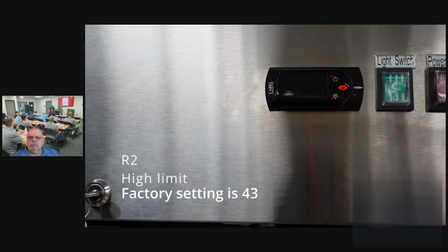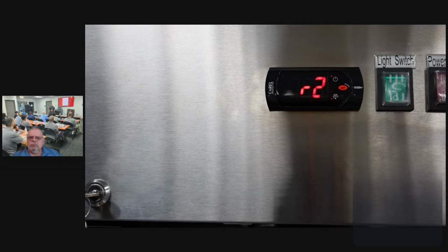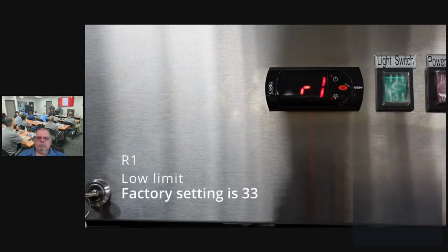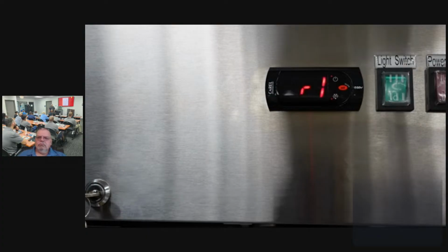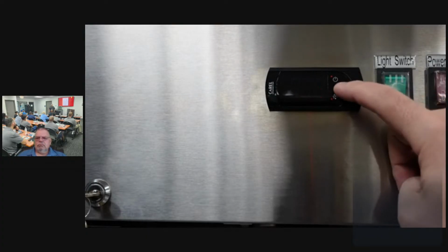The next one we'll see is R2. R2 is the high limit. The high limit is the highest temperature you could set this unit to. The factory setting is 43, which means you will not be able to set this temperature higher than 43 unless this parameter is adjusted. The next one we'll see is R1. R1 is the low limit, which is the lowest you'd be able to set the temperature to. The factory setting is 33 degrees.